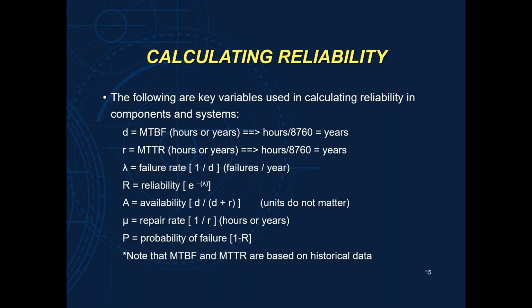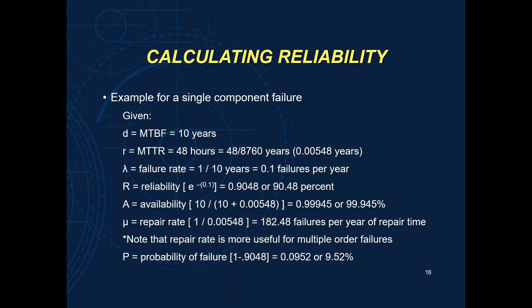So we have our formulas here, and I do have a quick little example for a single component failure. In this case, we have a mean time between failures of 10 years. So we have a component that fails every 10 years. What would you expect your failure rate to be? Well, 0.1 failures per year. That's pretty obvious. Mean time to repair for this particular device, we're going to say is 48 hours. So when you calculate your reliability value, the reliability calculates out to be 90.48%. What that means is, if you look at the very bottom, it's the exact opposite of your probability of failure. You have a probability of failure of 9.52%.